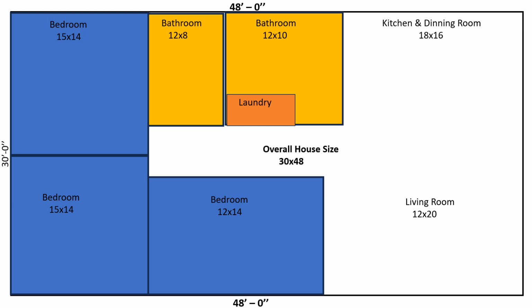And then some people were even going 600 and 750 and all kinds of numbers, but ICP generally wants 500. So if we look at this house, we see it is 30 by 48, divide it by 500, and that comes out to be 2.88. Now, some people would look at that and say, okay, I could go with a 2.5, which is a little under, or I can go with a 3-ton. So in this situation, we're going to take a look at the numbers between a 2.5 and then a 3-ton.